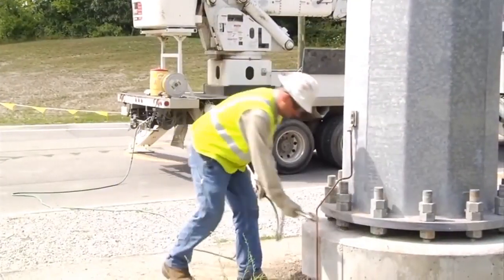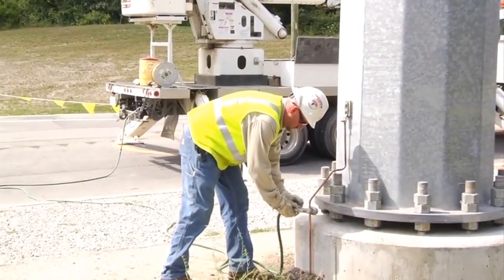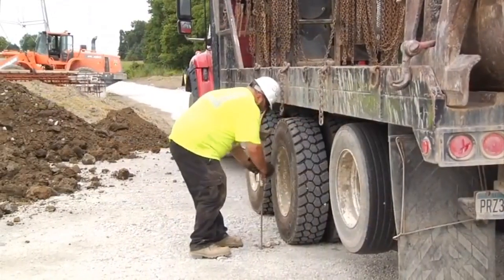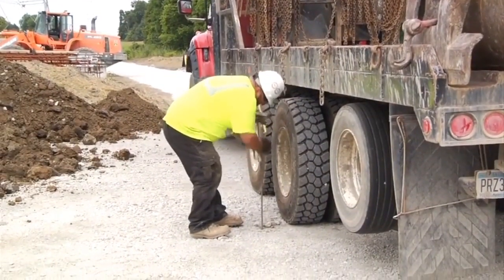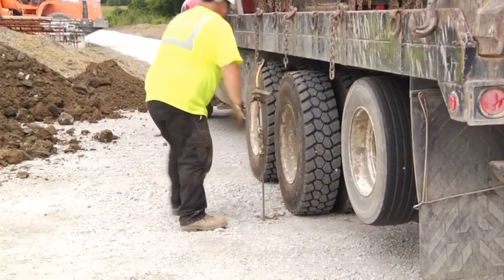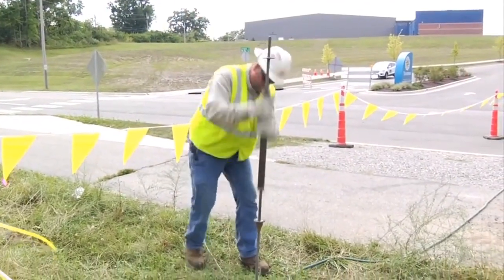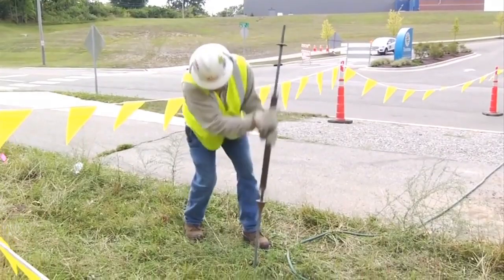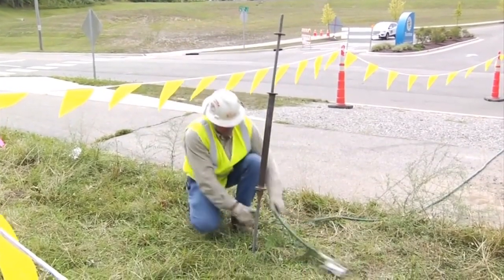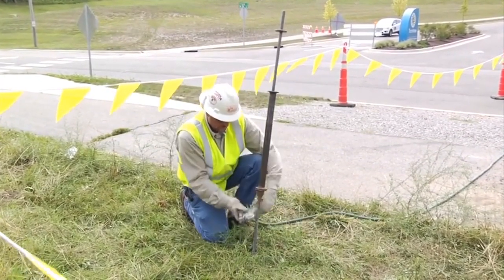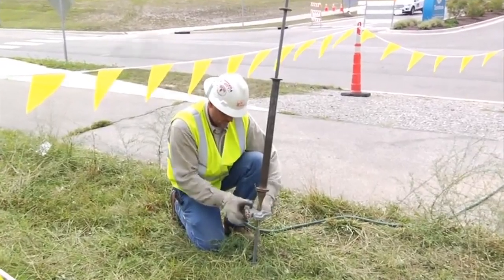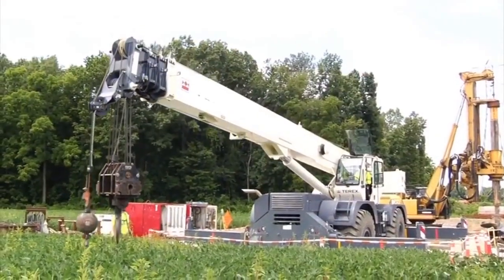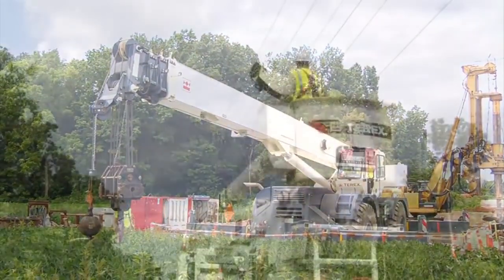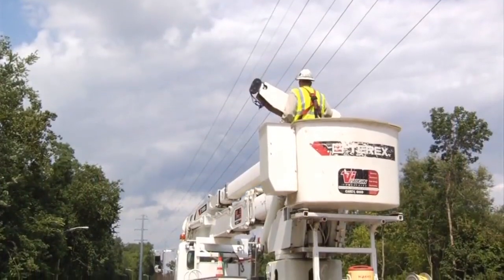When any aerial devices are in use, they shall be grounded. Where permanent grounding sources are not available, a remote temporary ground rod or an anchor shall be used. When a temporary ground rod is used, it is to be driven into the ground for its entire length if possible, but never less than 2 feet into the ground to provide the best ground contact. And equipment with a boom, mast, bucket, or bed shall be stowed and fully cradled before moving.